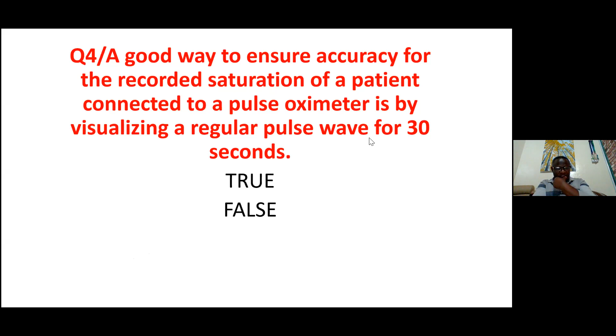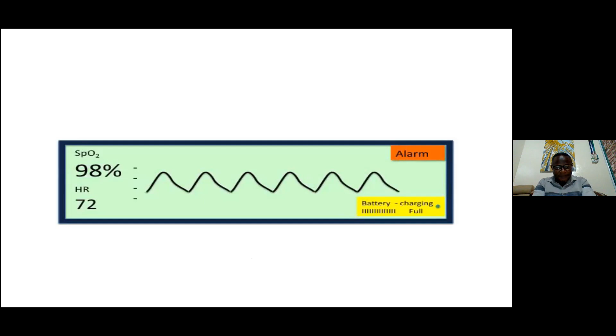So you see, when you put your pulse oximeter on the finger, sometimes you just have a number. That number can be low or high, but you don't see the curve very well, or it's not regular, it's not sinusoidal like this one. By the principle of functioning of the pulse oximeter, you have to have a sinusoidal curve because it is about a fraction of two numbers. So you need to have such a curve, which is sinusoidal, then you can confirm the number you are seeing. And you need at least 30 seconds to watch a normal curve and stable number, then you can confirm that you are on it. Next. So it's true.